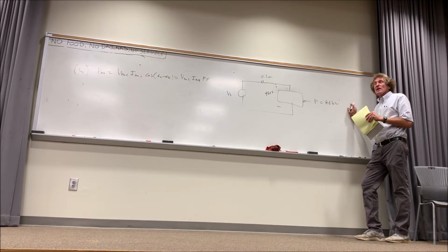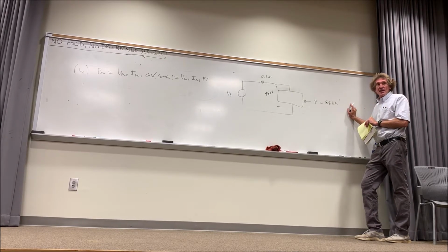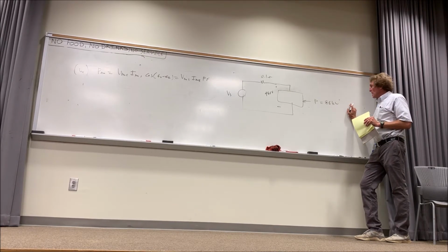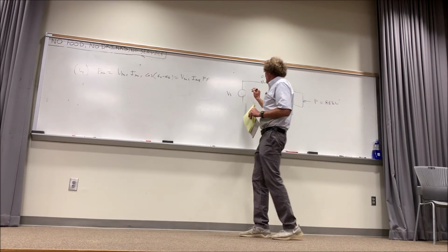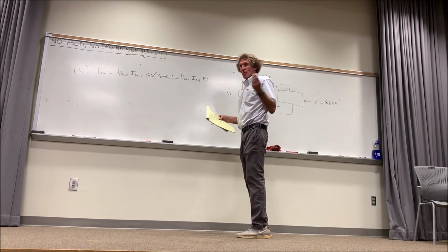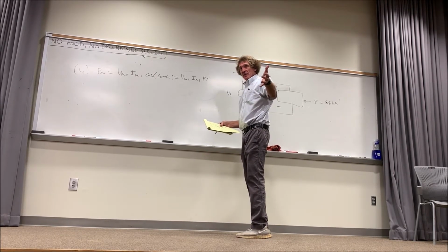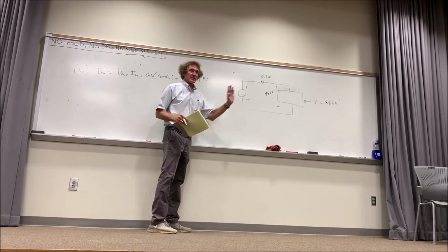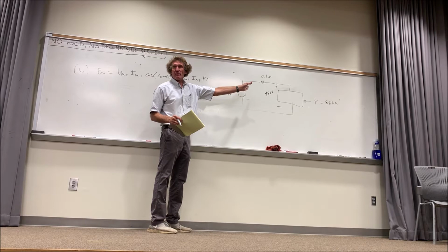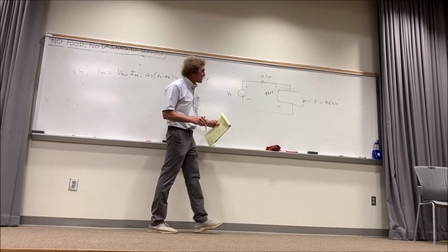By the way, this is more of a non-residential application. It's not quite there yet, but it's going towards an industrial type of application. So I've got a power dissipated there of 88 kilowatts, and it's at 60 hertz. Now I want to know what the voltage is back here at the actual source point. That would be a voltage downline that is regulated, but this is something we've got to calculate. Don't worry about why or how. Here's how we do it.